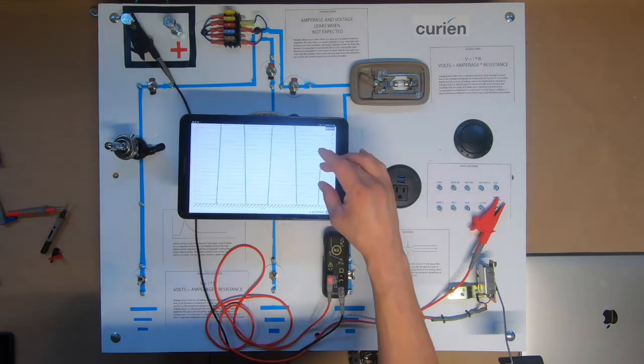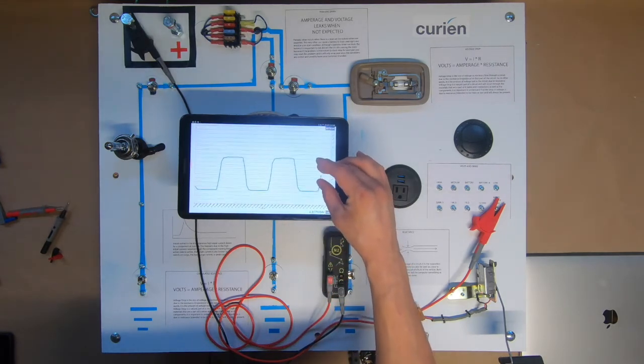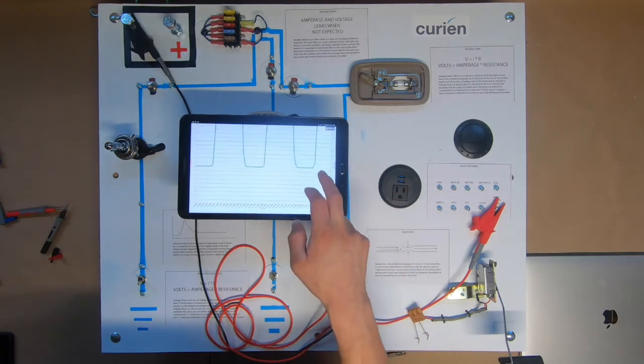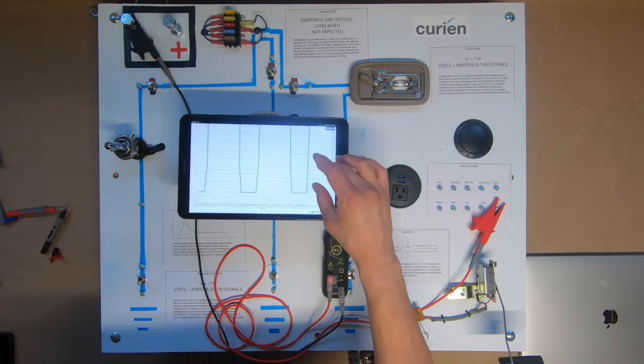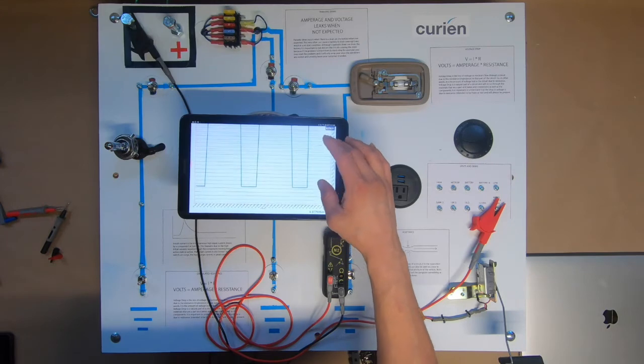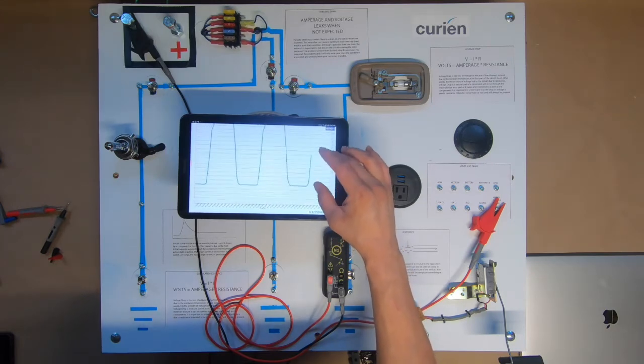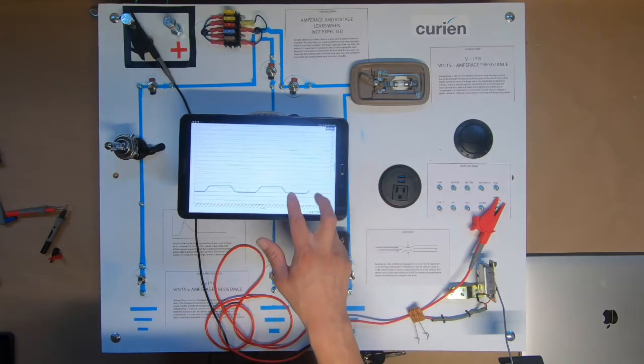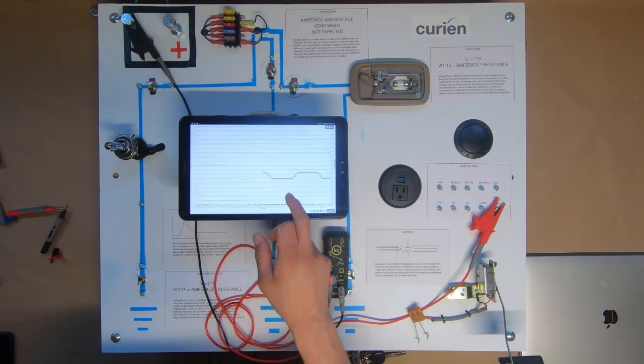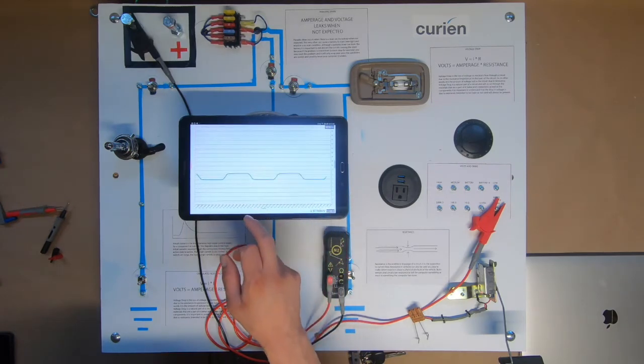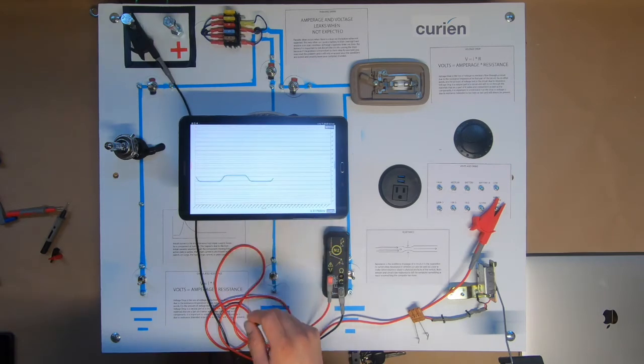So now I'm in manual ranging so I can zoom in and out on the particular signal. I can watch how long the signal stays at 3 volts. I can go up and watch how long it stays at 9 volts. In the RMSing that the meter side does, of course I would read in at the 6 volts.